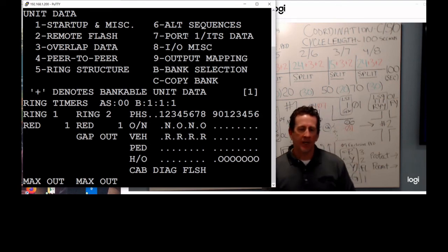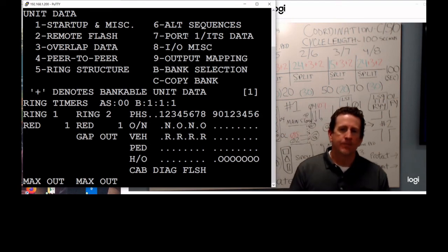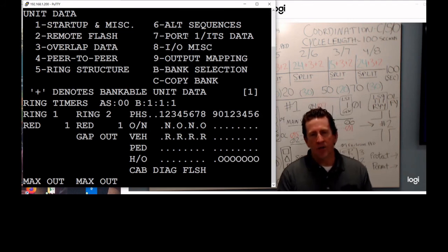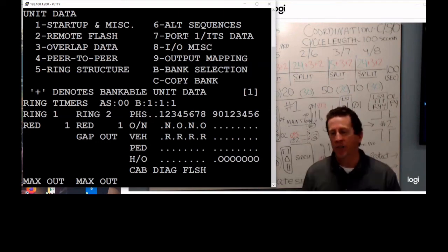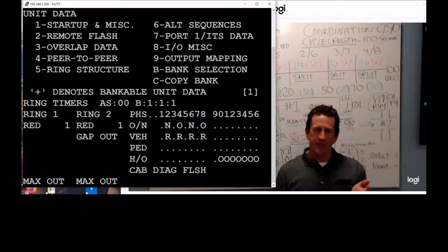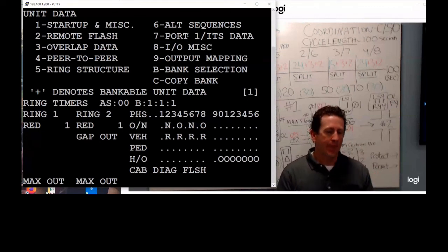The problem with the termination block is there's 8 wires that you need in there. And so 8 times 5 is 40. That's 40 more termination points in a cabinet that you don't need, 40 more potential chances for failure. We sell a lot of hub assemblies and SDLC cables that agencies put in other manufacturers' cabinets for that one reason. It was just a really good concept that they came up with.